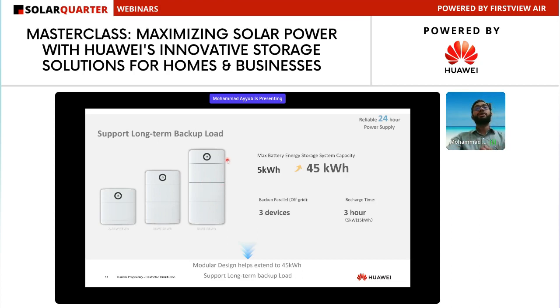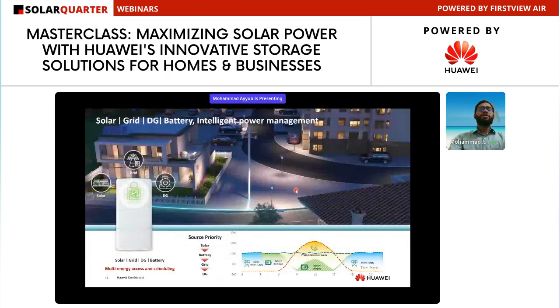We can connect up to 3 in parallel, which will make the overall capacity 5 kilowatt by 45 kilowatt hour. I will explain that configuration in more detail. The main advantage is that the system is modular in nature. Based on customer requirements, we can add more battery modules and provide the required backup power. So if we take one example where we have solar, grid, DG, and battery, we'll see how the system works in this example.